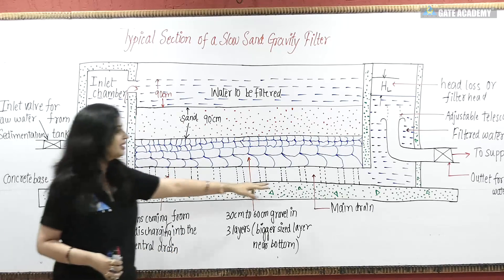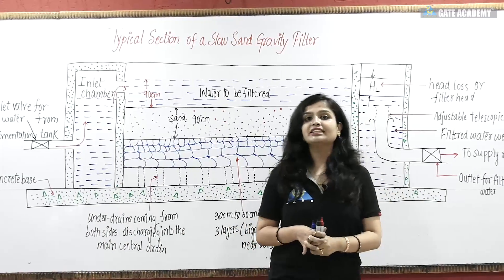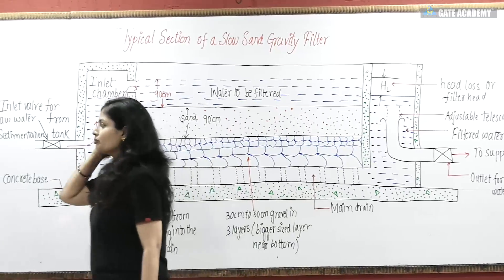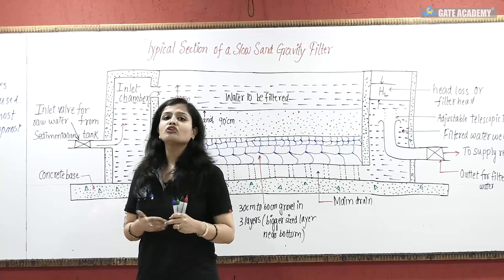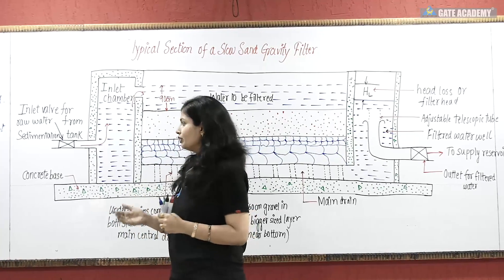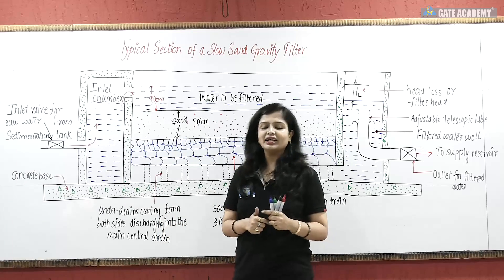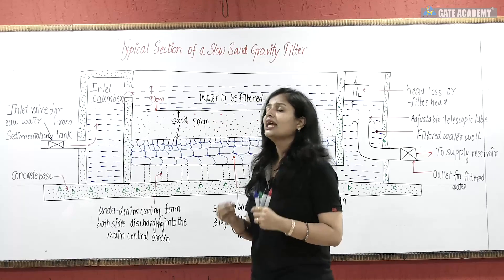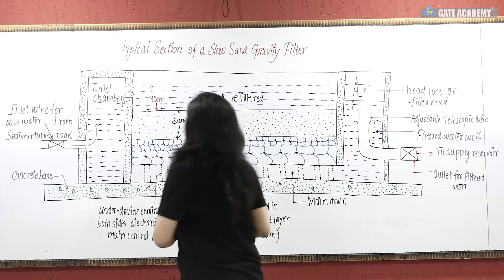Above the base we have lateral drains and a main drain. There is also an inlet arrangement and an outlet arrangement. Regarding sand particle sizing: the D10 effective size is 0.2 to 0.4 mm for slow sand gravity filters. The uniformity coefficient CU, which is D60 divided by D10, has a different value in slow sand gravity filters compared to rapid sand gravity filters. Head losses are also important and will be covered in numericals.